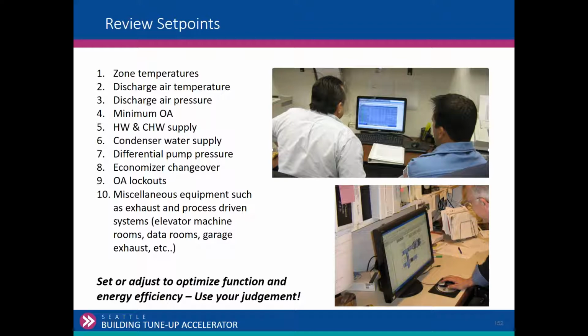If they have variable speed pumping, differential pump pressure, does that set point make sense? Economizer changeover. There's some dry bulb economizers right now in the Washington State Energy Code. The changeover temperature is 75. A lot of people don't know that you're required to use economizer until the outside air temperature goes above 75. The problem is that generally you can't meet your load, especially with DX cooling systems. So, does the economizer changeover temperature make sense?